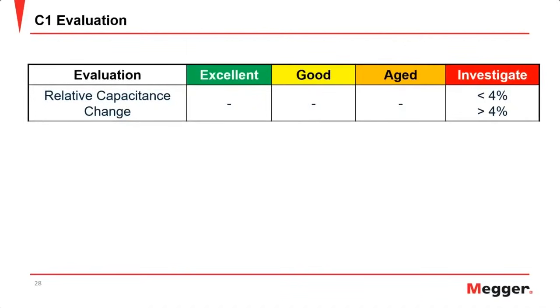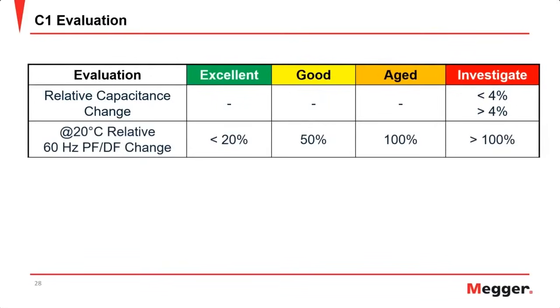Bushings, the way that they're capacitively graded, should not change over time. So any significant change like this should be investigated immediately for the health and safety of that transformer. Next, we will look at the power factor or dissipation factor change. We will start out by looking at the 60 hertz value, and it's important that the value is corrected to 20 degrees C. I talk a little bit later about how 20 degrees C temperature correction works. But what we're talking about with this is, again, the relative change.